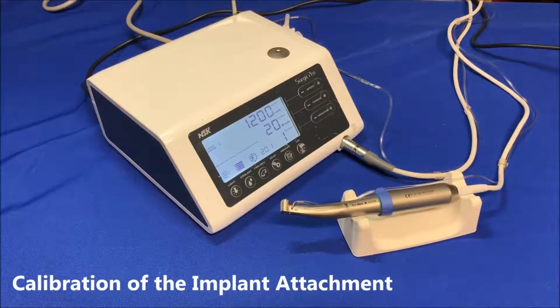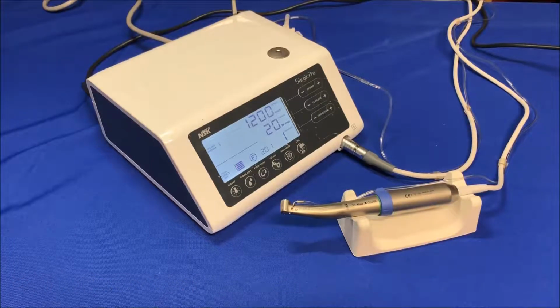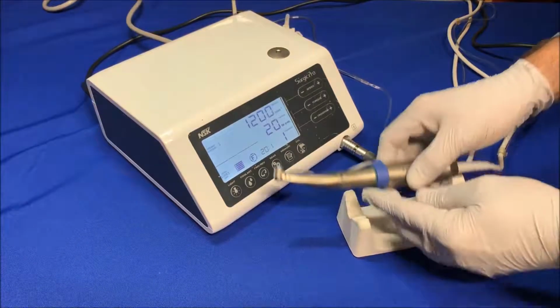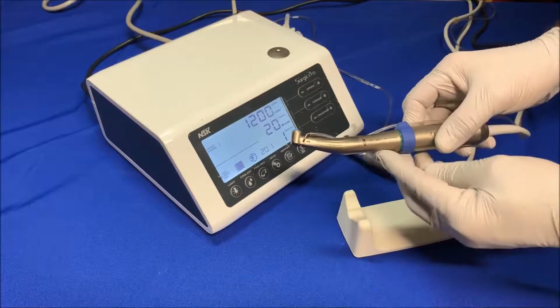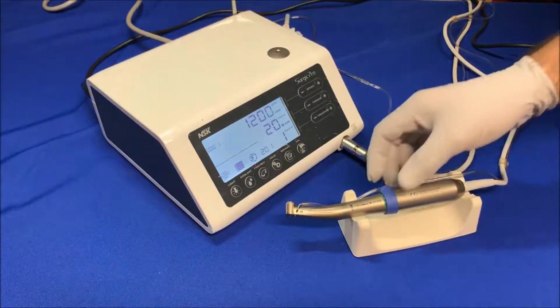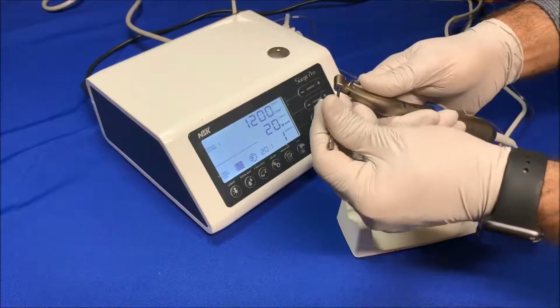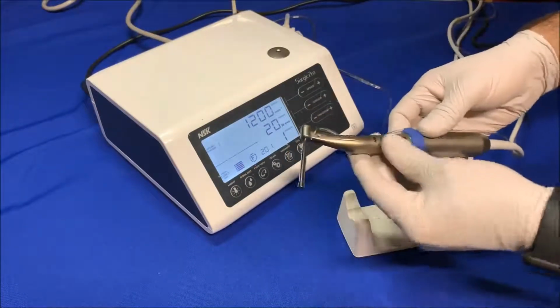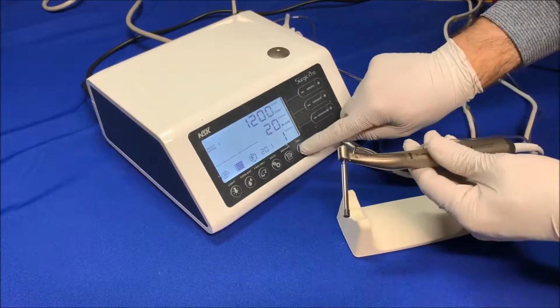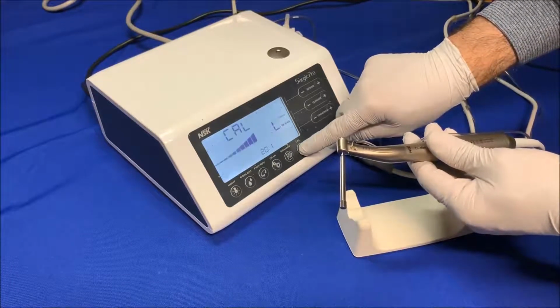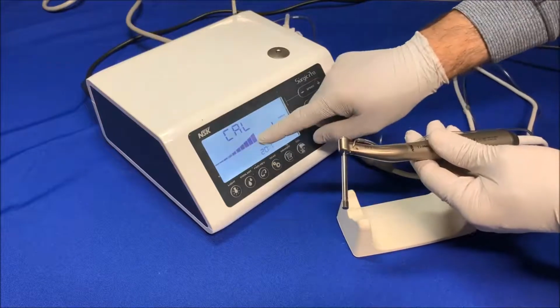Calibration. Calibration is aligning the spec of a used or new attachment with the control unit to make sure the accurate amount of speed and torque is delivered through the attachment to the drill. As the handpieces get old through normal wear and tear, or when you want to use a new attachment with the motor, you'll need to perform calibration. Attach the 20-to-1 handpiece to the motor and insert the calibration drill into it. Press the calibration key for about 2 seconds. A long beep will be heard and the display will turn to calibration.